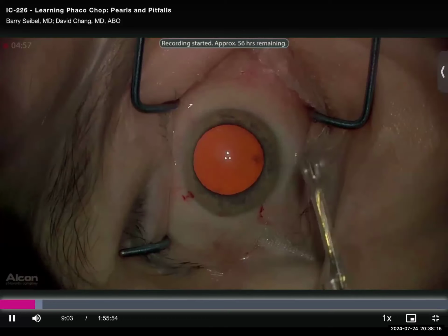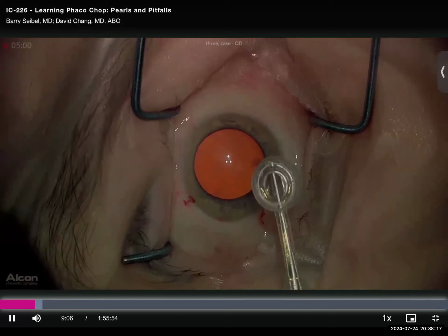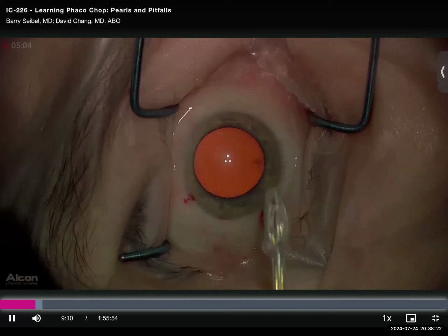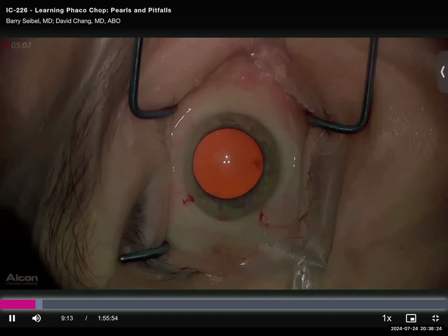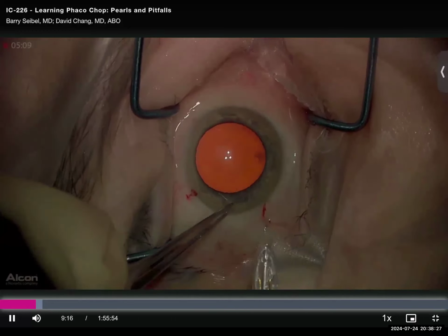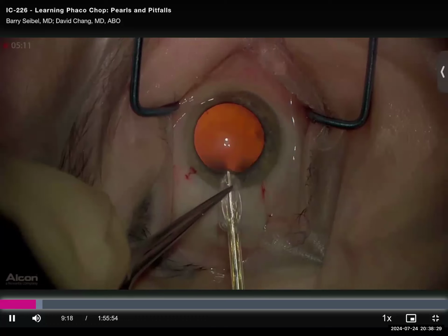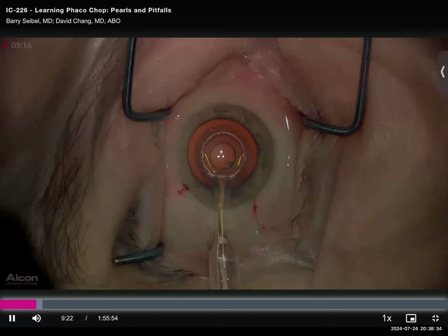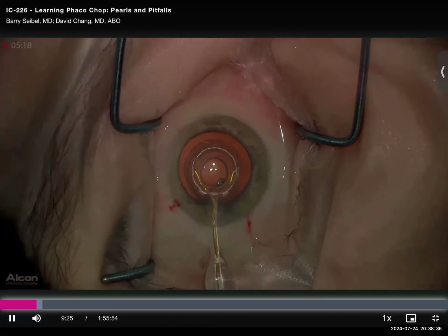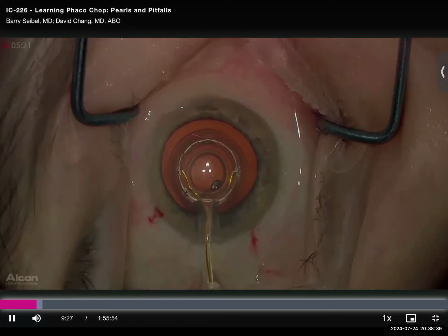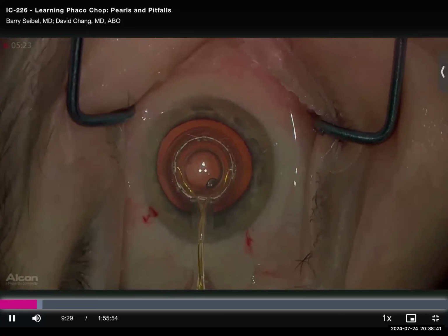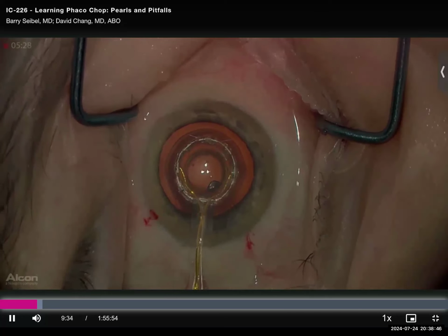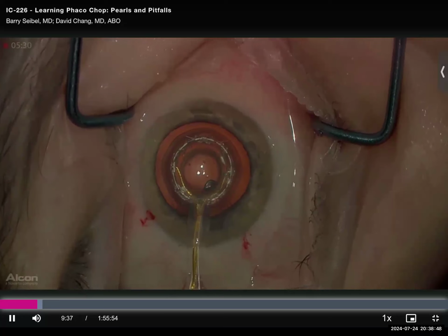Yes, and so this is, for those that haven't seen it, Zepto. I actually do consult for them, and what it is is an automated capsulotomy without the need for a femtosecond laser. So it folds, goes through a clear corneal incision, and then that rod comes back, and the ring itself is nitinol. It doesn't cauterize, it vaporizes. So there's a heating. It's a very instantaneous, brief moment of heating, and that causes vaporization, and you'll see a little bit of just a subtle jolt here in a moment.